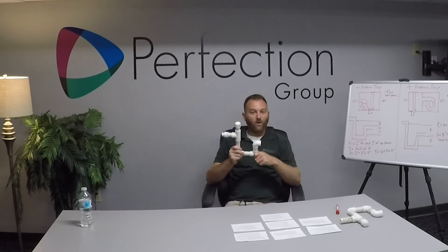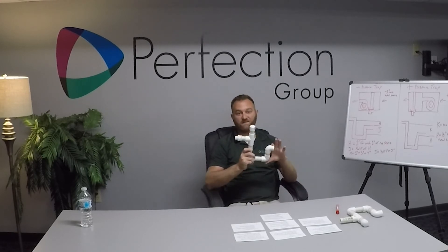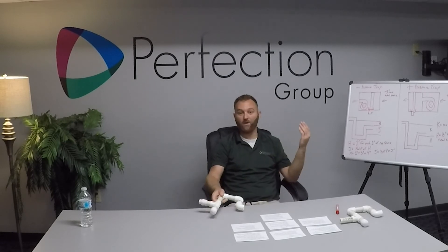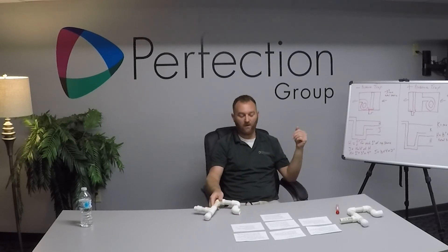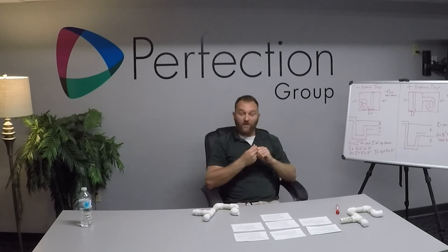Be very aware of plenum return ceilings. PVC is typically not allowed in a plenum return, which is open above the ceiling. Codes typically require copper or CPVC — check the plumbing codes and fire codes for that. Thanks for watching and see you next time.